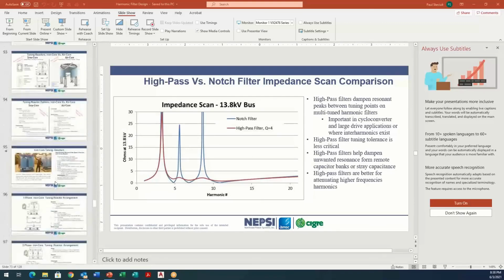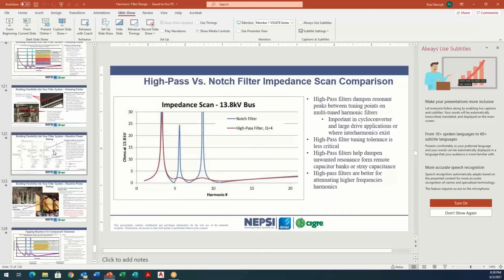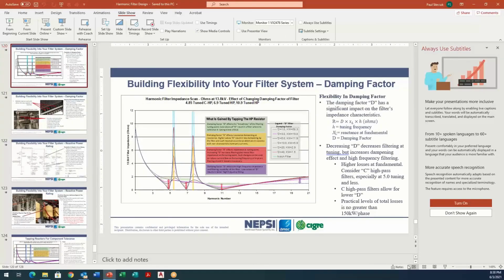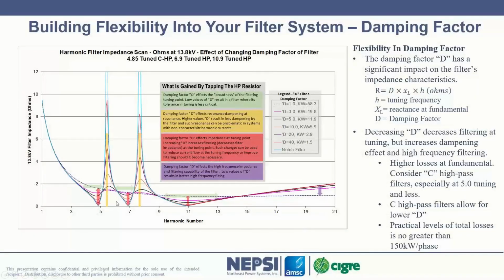Yes. So we'll answer that real quick with this figure here. Perhaps you can see it, but as I change the damping factor of these three filters, you can see the impedance characteristics of the filter significantly change. So yes, it has a big difference. In this case, the first filter branch is a C-high pass. But remember, whether it's C-high pass or high pass, the damping factor is going to have an effect on it. Again, remember, with C-high pass filters, at the tuning point and below is where you typically see it.